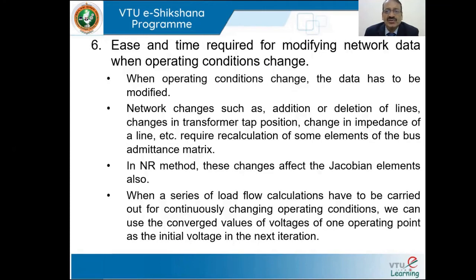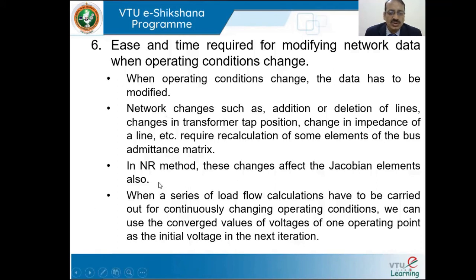Ease and time required for modifying network when operating conditions change: when operating conditions change, the data has to be modified. Network changes such as addition or deletion of lines, changes in transformer tap position, change in impedance of the line, etc., require recalculation of many elements of the bus admittance matrix. In the NR method, these changes affect the Jacobian elements also. When a series of load flow calculations have to be carried out for continuously changing operating conditions, we can use the converged value of the voltages of one operating point as the initial voltage for the next iteration.